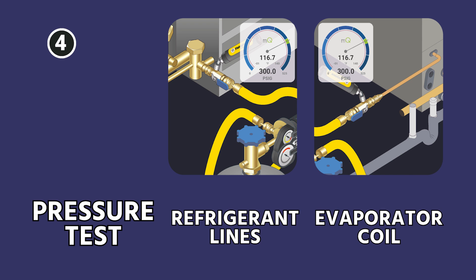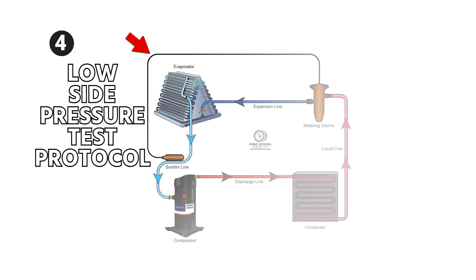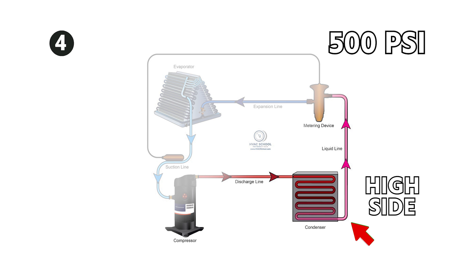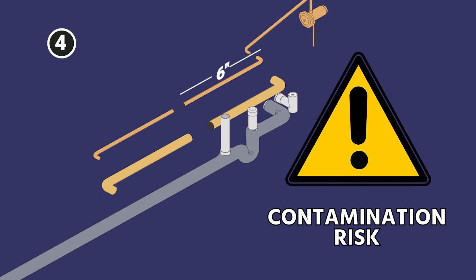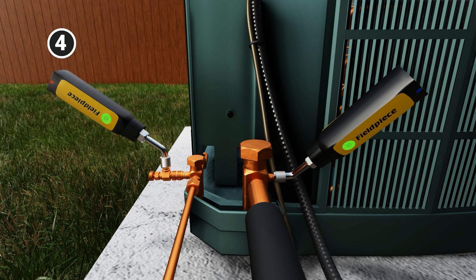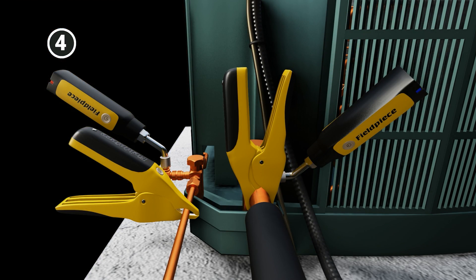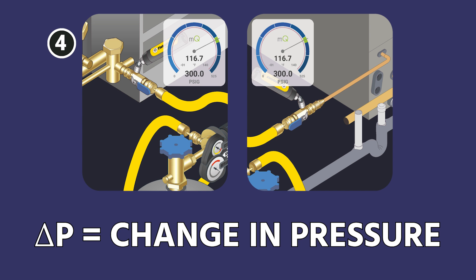I like to pinch off both sides and put a Schrader core in the evaporator side so you can pressurize each line individually and also pressurize the evaporator coil separately. You can pressure test both the refrigerant lines and the evaporator coil — I say 300 psi in this guide, but follow the low-side pressure test protocol on the evaporator coil. On the high side you could go up to 500 psi, but you don't want to go higher than that because you risk pushing nitrogen through your service valves and contaminating refrigerant in the condenser. Use a fine instrument like Fieldpiece Job Link probes to monitor delta P — change in pressure — over time, with one probe on each section.